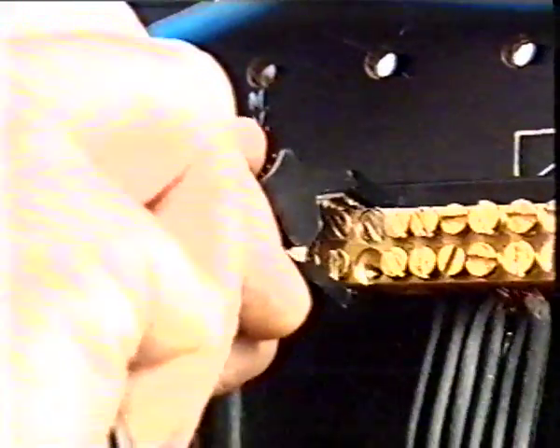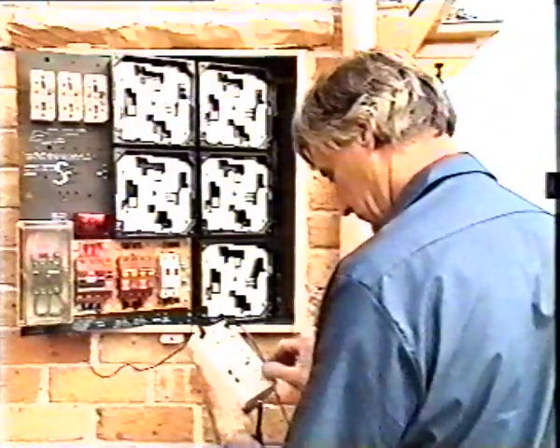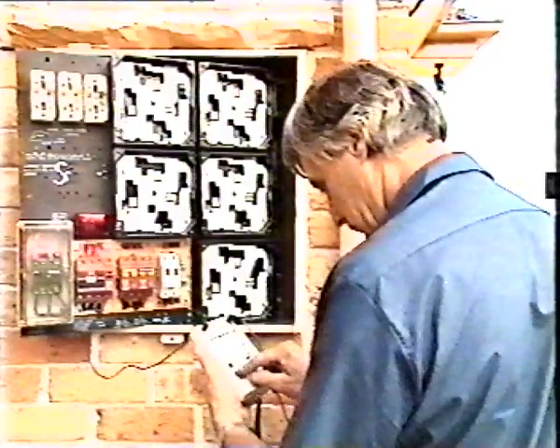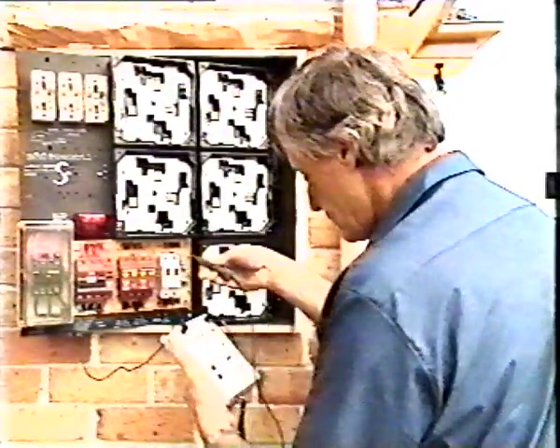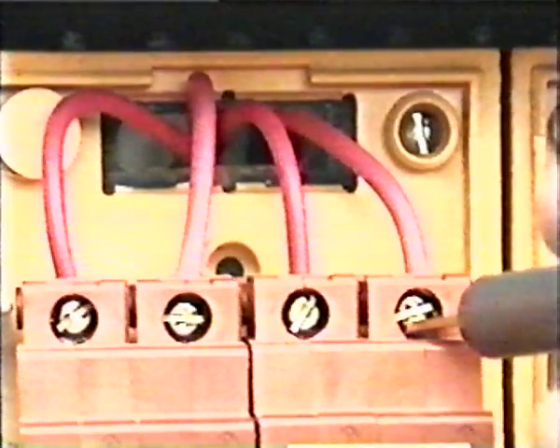In this test, we need the ohm meter. Testing should be conducted between the active and the neutral conductors of each circuit at the switchboard. The circuit will be identified by its typical resistance. It's important that each circuit be tested individually. These tests are usually conducted in conjunction with the other tests.